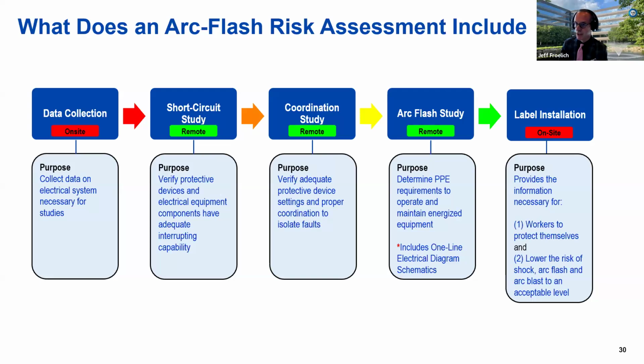They're going to start from the utility services and work their way down through the electrical system, collecting information on voltage, various fault currents, wire sizes, components like breakers and fuses, overcurrent protective devices, and they'll work their way through the primary, secondary, the bus system, everything from A to Z. At that point, we move into the short circuit study.